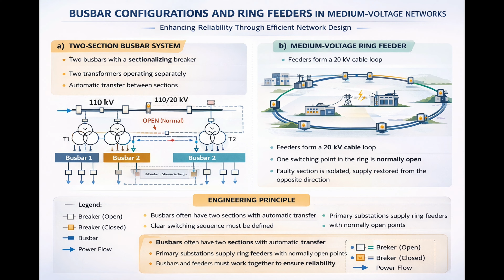As an engineer, your task is to ensure that the normal operation configuration is clearly defined, the reserve switching sequence is predefined, protection settings match both normal and reserve states, and equipment ratings support temporary overload during the transfer. When these conditions are satisfied, the medium voltage ring feeder becomes a robust and efficient distribution solution.